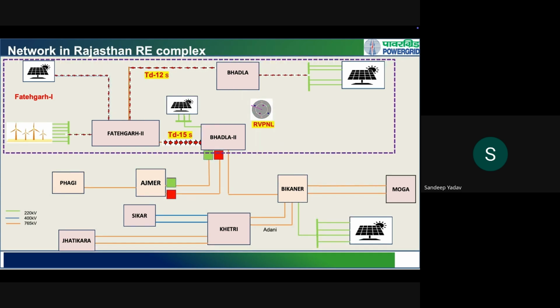So this was one of the systems. Most of these generators, PV and wind, are connected to Fatehgarh 2. A lot of PV generation is connected to Bhadla, and all this power comes down to the Fatehgarh station, and from Fatehgarh 2 it comes down to Bhadla 2, and from Bhadla 2 it goes to all other 765 kV substations to feed the load centers. Now, if the regional overvoltage strategy is not planned properly, what will happen is that the outgoing lines, for example this particular line from Fatehgarh 2 to Bhadla 2, carries all the load which is coming from Fatehgarh 2 and Bhadla.